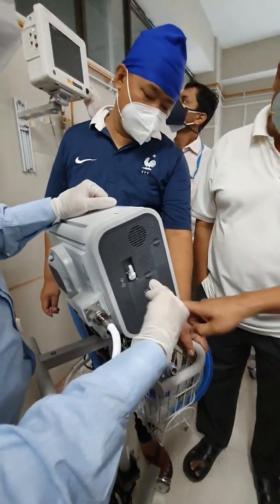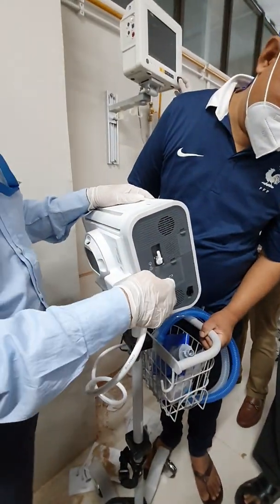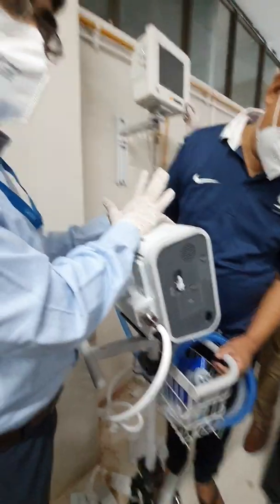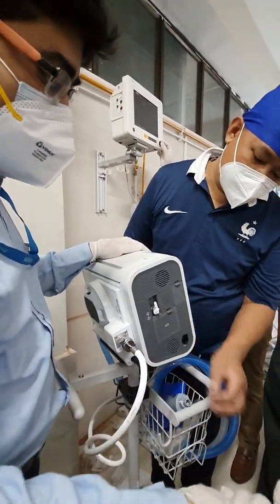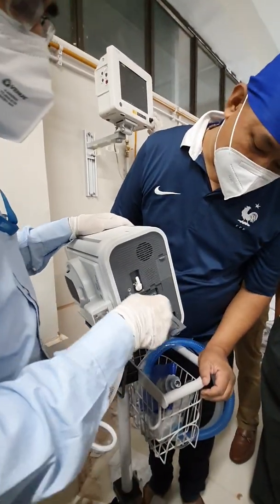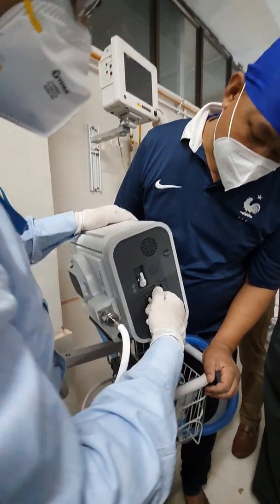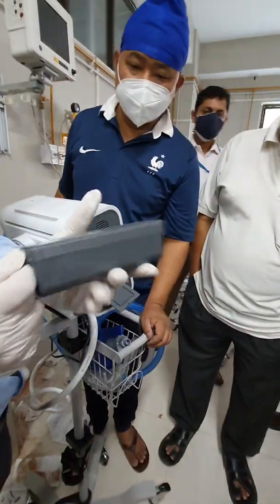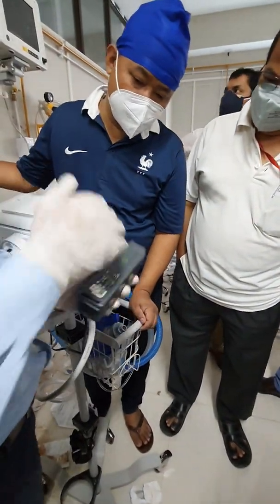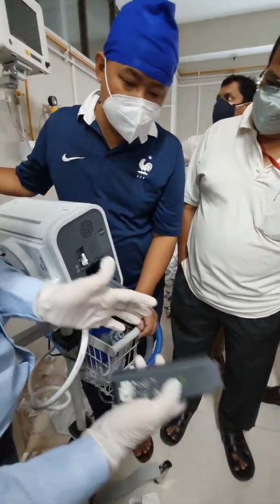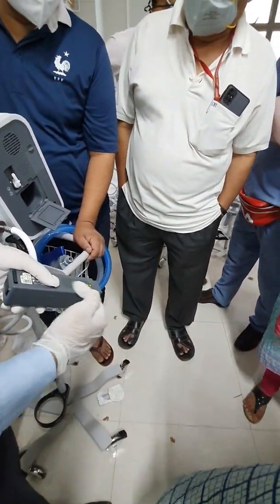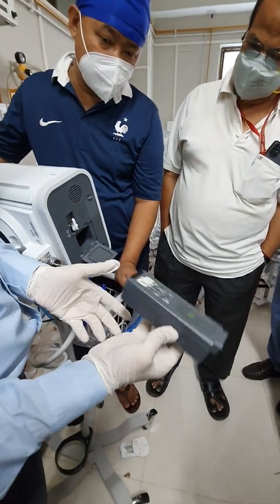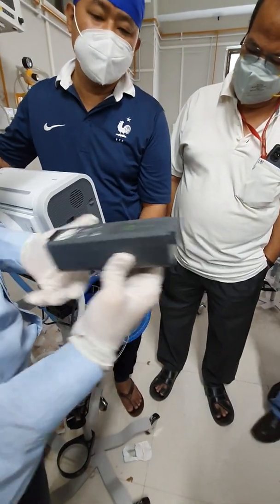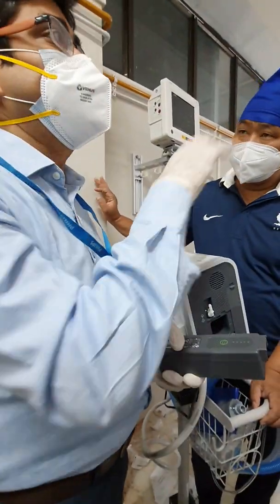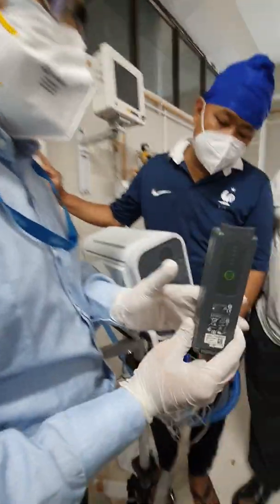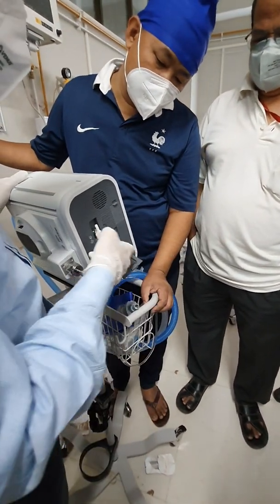Okay. Now this is called the external battery. We have two batteries: one is inside and this is external. If you open it, you will get a battery which we call hot swappable. Why hot swappable? Because if you take this out, the machine will automatically shift to the internal battery, and the machine will not stop. You can see this is fully charged right now. It has a capacity of 7.5 hours of backup. If I include the internal battery, this is 15 hours of battery backup in total. Very easy to place. Just place it.